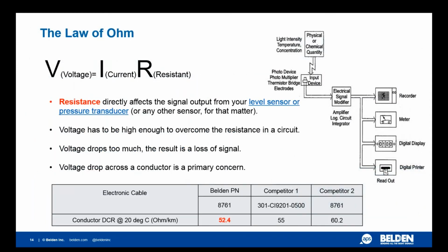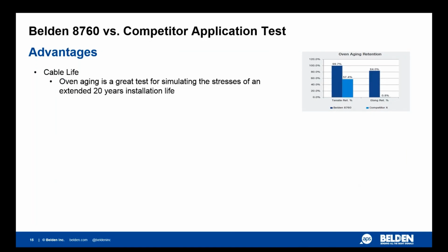We then come to resistance, which directly affects the signal output from your level sensor, your pressure transducer, or any other sensor for that fact. Voltage has to be high to overcome the resistance in a circuit. If voltage drops too much, the result is a loss of signal. Voltage drop across a conductor is a primary concern. So as you can see in the table below, Belden's classic cable 8761, we have 52.4. Competitor 1 is 55, competitor 2 is 60.2. This all leads to the advantages against our competitors.